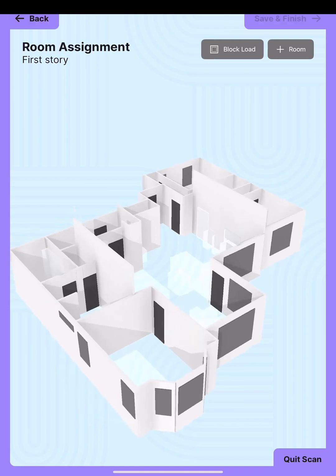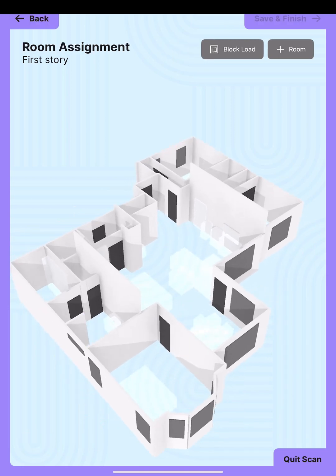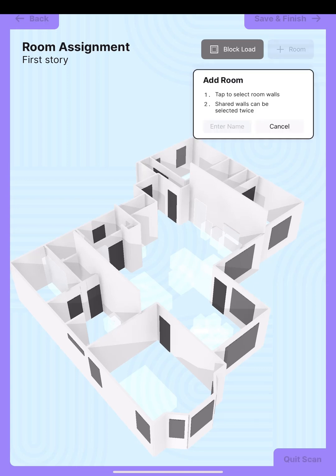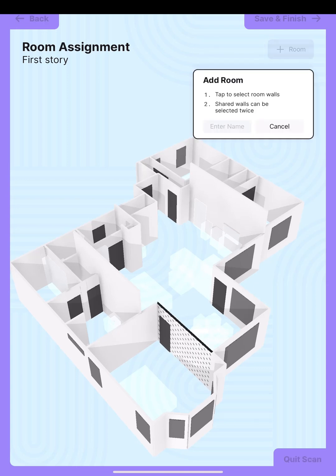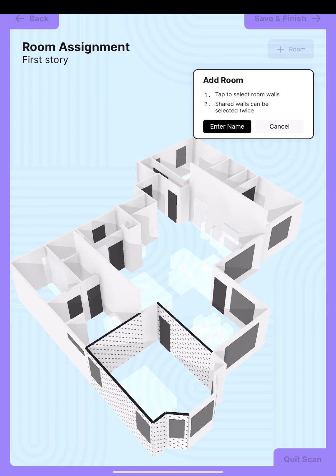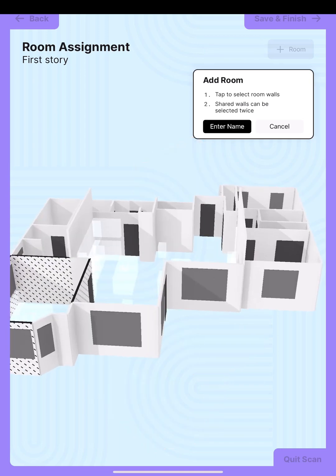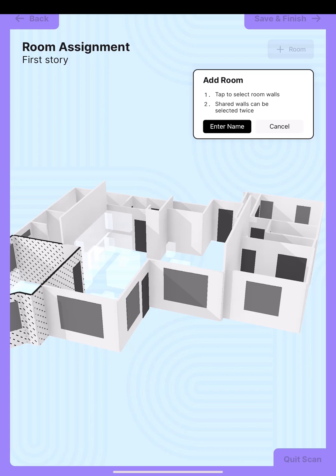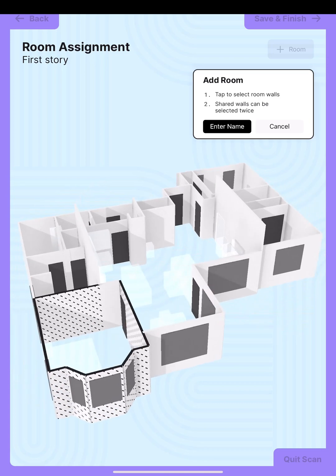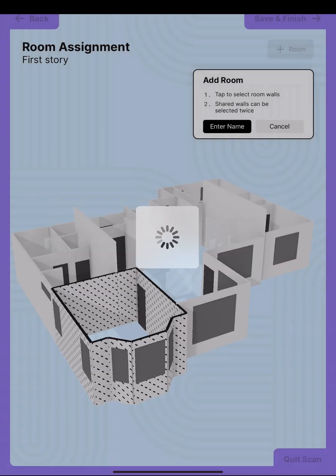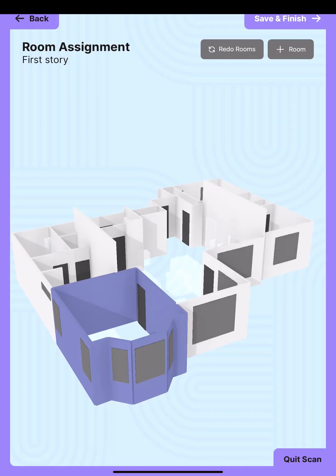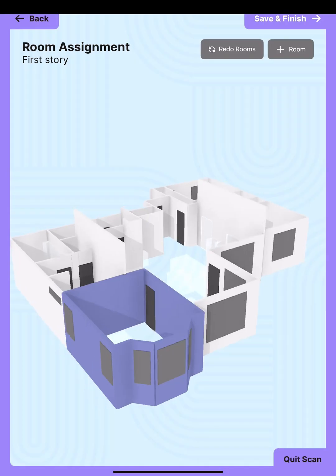The next step is room assignment. You have two choices: you can do a block load where it treats everything like one room, or you can start telling it which rooms are which. We're going to add a room here and select which walls are part of that room. Here's our master suite — we're going to select these walls. If you're doing a ductwork replacement or a new system install, you'll want to do a room-to-room. But if you're just doing an equipment replacement, typically a block load is all you need. I'll repeat the same process for the rest of the house.